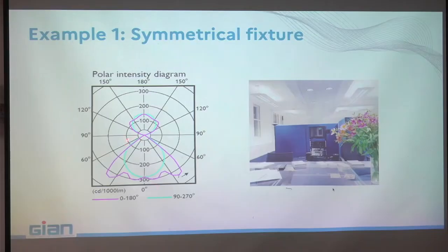When you see that you have a fixture that in that plan opens the beam at 60 degrees, and the height is not very high. That means here, as the distribution is very constant, you can illuminate very effectively and with a good uniformity just under the luminaires.